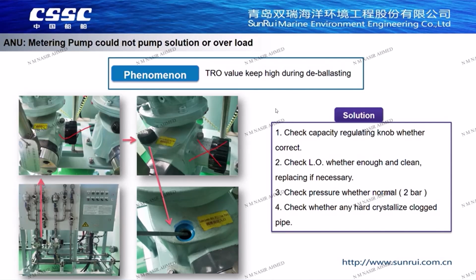When the pump is overloaded, check the lubrication oil of the metering pump, whether the lubricating oil is clean and sufficient. Replace the lubricant oil if necessary. Finally, also check the pressure gauge of the ANU. Usually, the discharge pressure is set around 2 bar. Another possibility is that the pipeline of the metering pump is blocked by salt crystallization, which can also be checked accordingly.